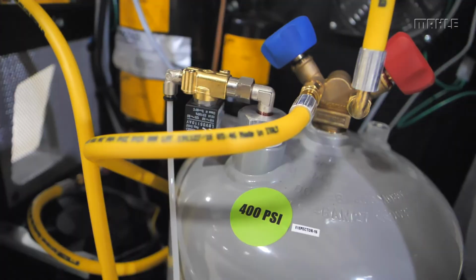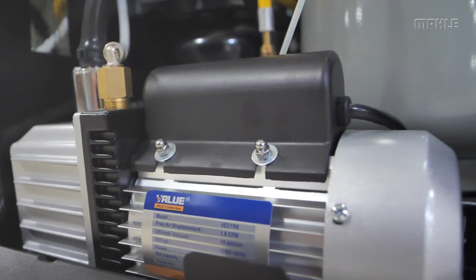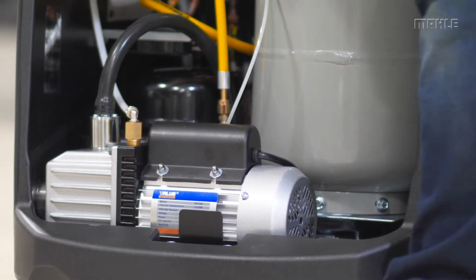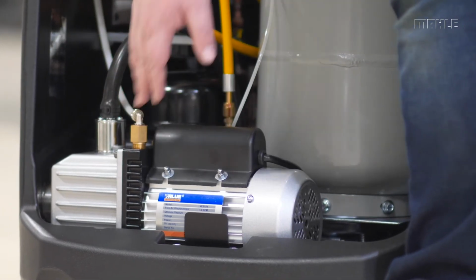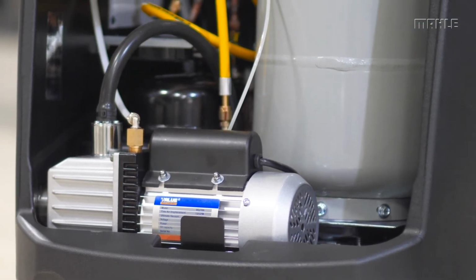And here we have the vacuum pump. It's easily accessible for vacuum oil changes. And over on the side of the unit, we have a sight glass that allows you to check the level of the vacuum pump oil.